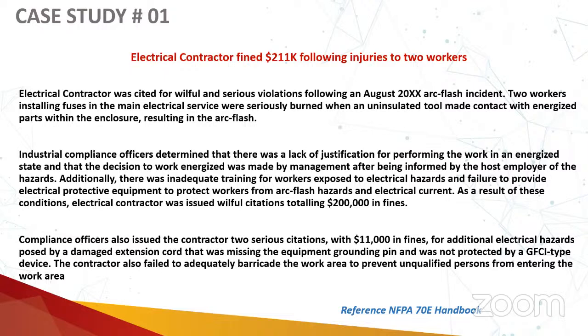So neither of these protections were given, and as a result of this, non-contact testers were also not provided. If the non-contact testers would have been provided, probably they would have checked whether the insulated tools were functioning or not, and whether the circuit was energized or de-energized was not justified properly while performing this work on the electrical equipment, and all this resulted in an arc flash hazard.